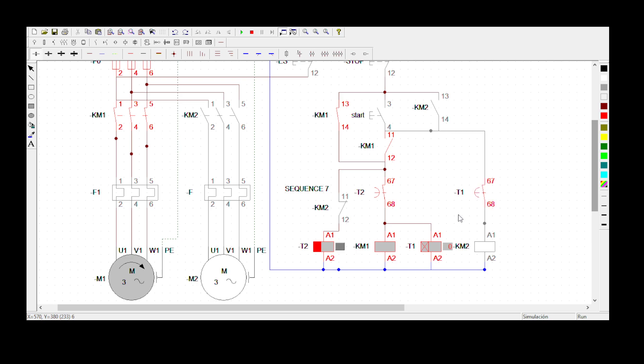The normally open is now a normally closed because the timer has finished counting. There's an interesting tricky part here - this was originally a normally closed contact of KM1. So when KM1 energizes, it immediately becomes a normally open so that power will not flow to energize KM2. We don't want KM2 to energize automatically after 10 seconds; we want it to energize only after you press the same start button again.